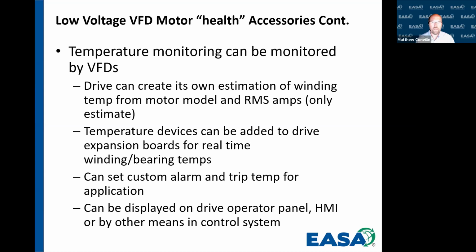So if we have a shaft mounted or integral fan, like a totally enclosed fan cooled machine, and we're lowering our speed, the actual winding temperature is going to be different than what the drive is estimating. So what we can do to account for that is we can use temperature detectors, and they can be added to the drive via expansion boards, and then we can monitor our winding and bearing temperatures. We can set a custom alarm and trip temperatures for an application.